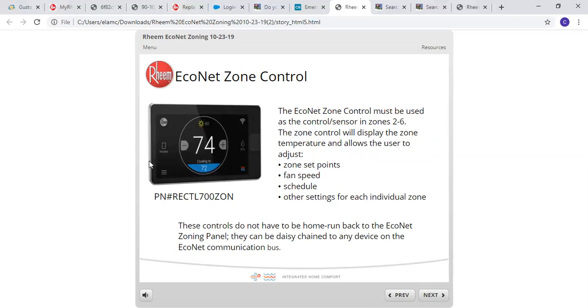This one right here looks identical to the Econet, but this is actually your zone control. Do not order separate Econets for each zone. If you do, they're going to basically battle for control of the system, and it will not operate correctly. So you have to have one Econet smart thermostat, then you have to have the zone stats. The zone stats will be used in zones 2 through 6. The zone control will display the zone temperature and allow the users to adjust set points, fan speed, schedule, or other settings for each individual zone. The part number on that is the RECTL-700ZON.